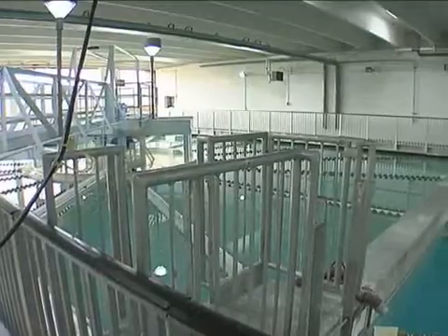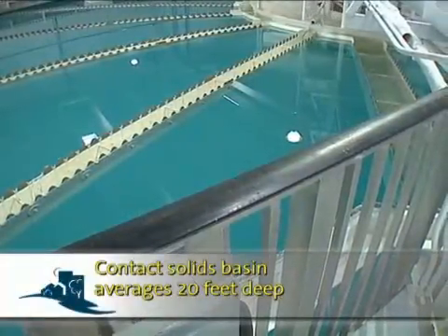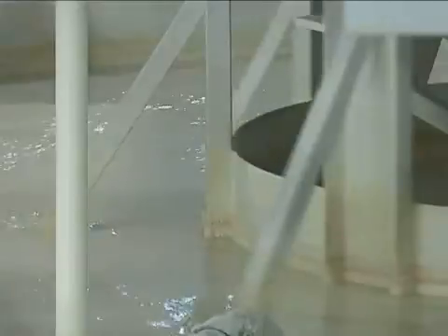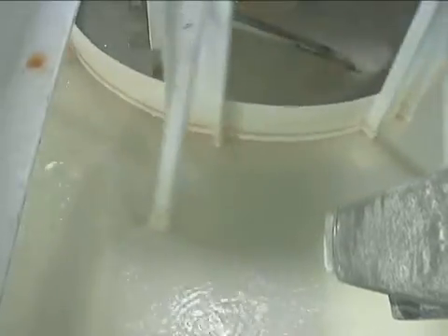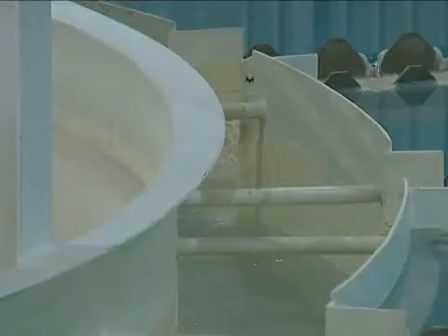Bloomington well water heads to the Sam Hobbs water treatment plant. The very first step is softening — raising the pH of the water so that hardness precipitates out. The water is softened in a large tank called the contact solids basin. Water starts in the middle, works its way down around a large cone and up to the top. A turbine spins to mix the water and help the chemical reaction go to completion. On the outside is a clarifier — as solids build up, they settle to the bottom. Wheel spokes grab the clearest water off the top and send it to the recarbonation basin.